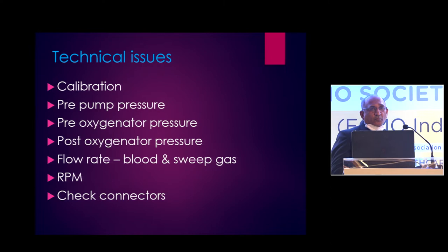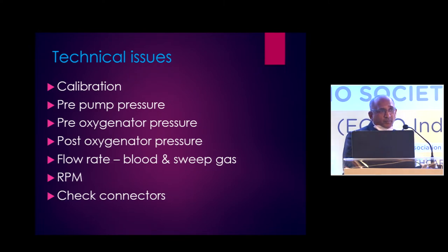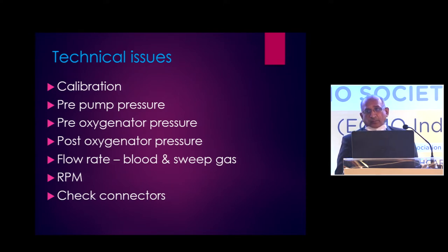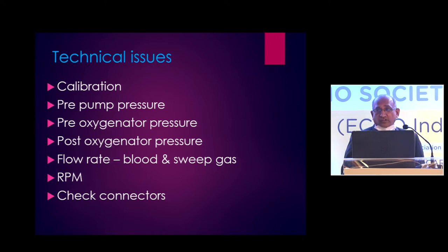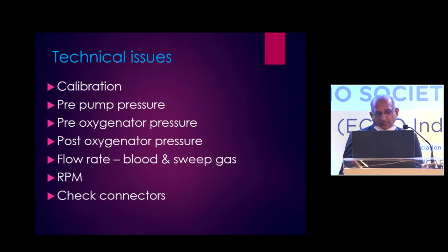Check RPM and flow rate — that is very important. As it is a centrifugal pump, your blood flow rate may not be the same as what you set with the RPM. With the same RPM the blood flow rate keeps going up and down, and that depends on preload and afterload. So if there is any change in preload or afterload, with the same RPM you might have a change in the blood flow rate. With the same RPM if the blood flow rate is going down, it means there is something wrong with the circuit. Check all the connectors — whether they are loose, as air can go inside or there can be bleeding from there.